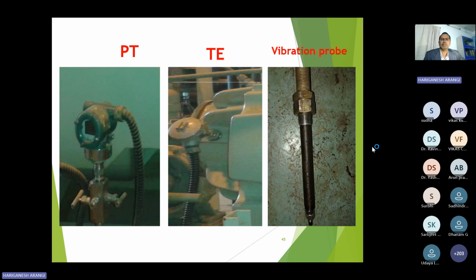The middle one is temperature elements. When the temperature rises high, that equipment will get tripped to avoid major damage. And the third one is vibration probes, where the equipment has to operate smoothly. If there is any abnormality, any high vibration, it will indicate and trip the machine to safeguard it.